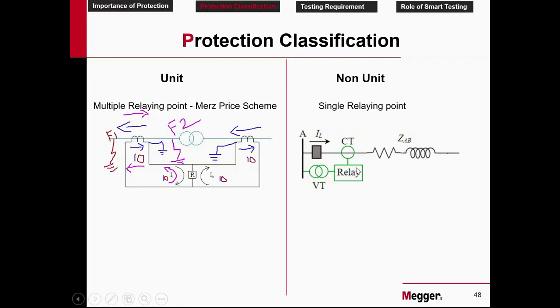This is going to calculate the impedance. So for impedance, you have two formulas. What are the formulas? Z is equal to V divided by I. You can also say Z is equal to R plus jX. So you have two formulas for impedance. Ohm's law, Z is equal to V by I. Another formula, Z is equal to R plus jX, resistance and reactance. So this we call as settings, ZS, set impedance. This we call as actual impedance or measured impedance, Zm.